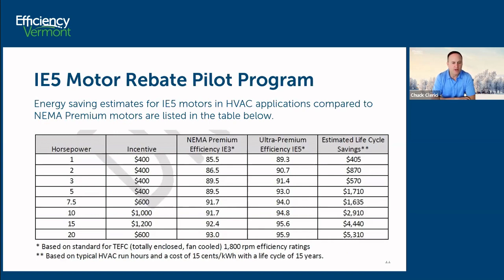You see it spans from 1 to 20 horsepower on the left-hand column. And the second column from the left, you'll see the incentive by horsepower. These incentive dollars are intended to close the gap between the cost of an IE3 motor, or NEMA premium efficient, and a new IE5 ultra premium efficient motor. So when you're looking at a motor replacement of, say, 5 horsepower, I'm just going to pick a number, maybe that motor is $800 and the IE5 motor would be $1,200. We're offering $400 to basically make it cost neutral and help you get the customer into the ultra premium efficient motor.